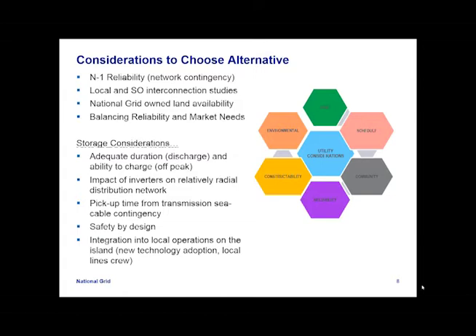It's an island, so it doesn't really have a network system - it's a very radially weak distribution network. We wanted to make sure the impact of the smart inverters on the network wouldn't cause new faults, and also that, because the energy storage was located at the Bunker Road substation rather than the Candle Street substation where the transmission cables connect in, the timing would be right so that if we lost one of the transmission cables, the Bunker Road substation's energy storage solution would detect that and be able to pick up that load relatively quickly.